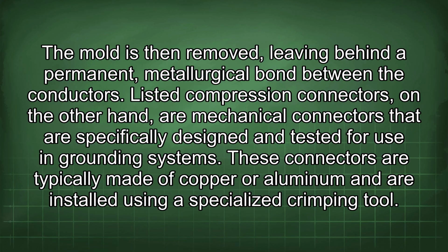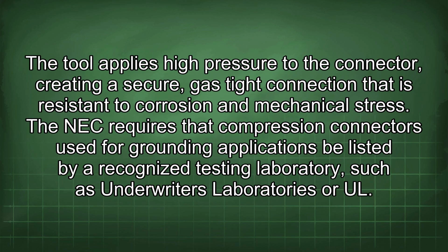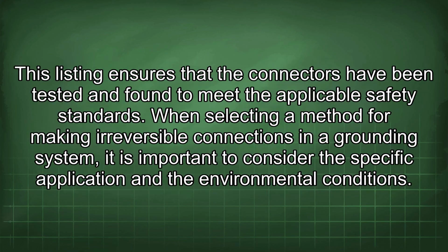Listed compression connectors, on the other hand, are mechanical connectors that are specifically designed and tested for use in grounding systems. These connectors are typically made of copper or aluminum and are installed using a specialized crimping tool. The tool applies high pressure to the connector, creating a secure, gas-tight connection that is resistant to corrosion and mechanical stress. NEC requires that compression connectors used for grounding applications be listed by a recognized testing laboratory, such as Underwriters Laboratories or UL. This listing ensures that the connectors have been tested and found to meet the applicable safety standards.